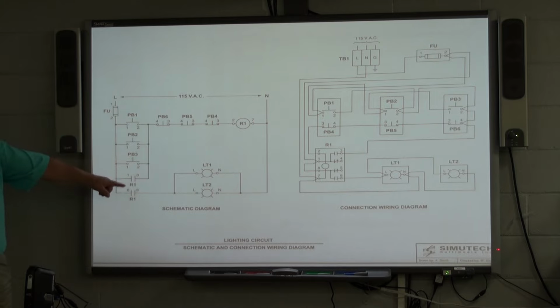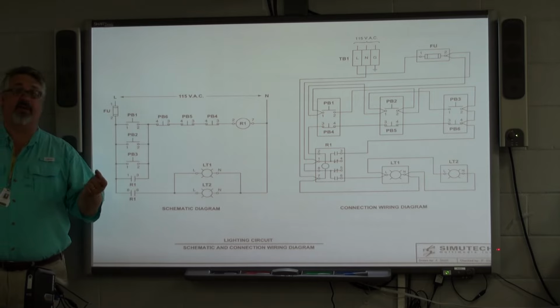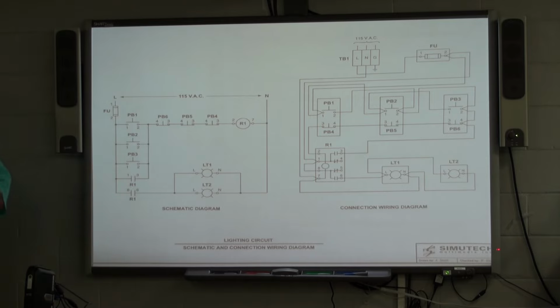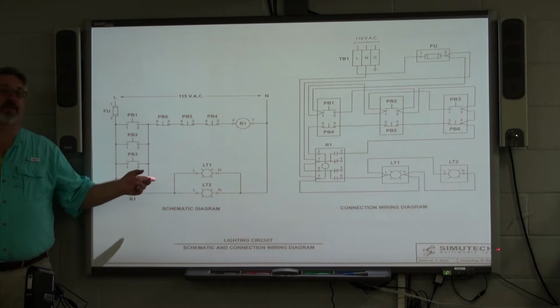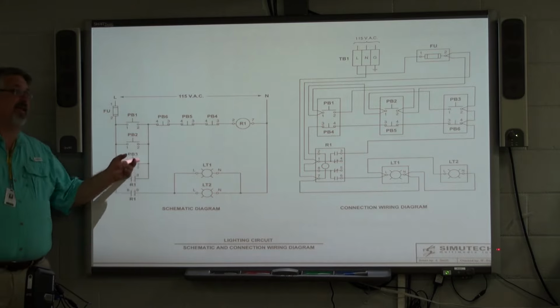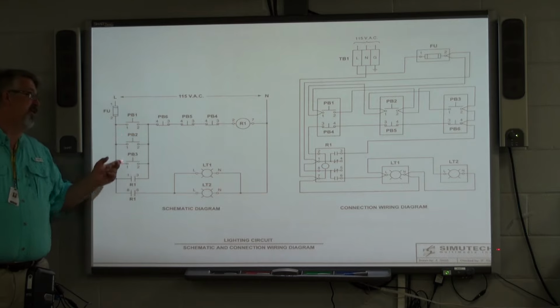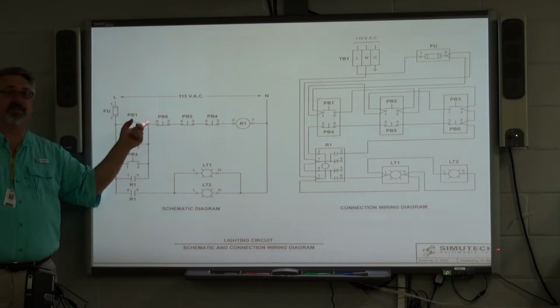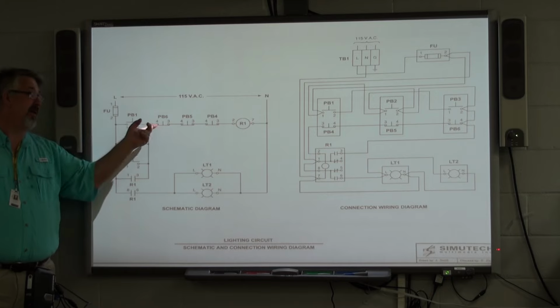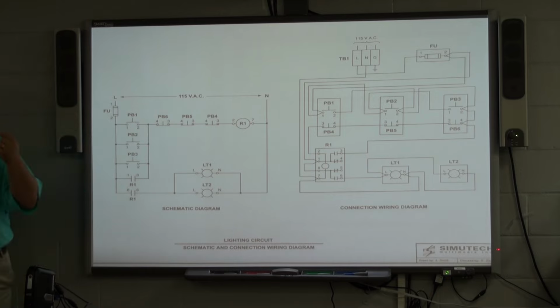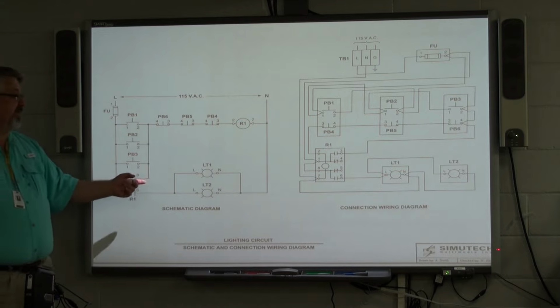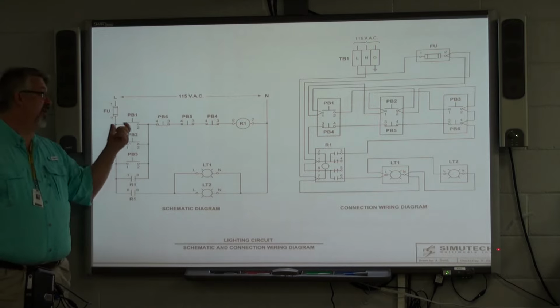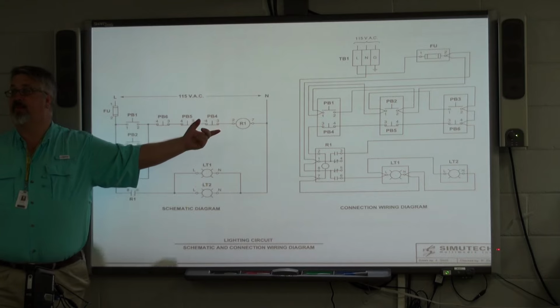Well, R1 and R3, our pin 1 and pin 3 of R1 are also contacts. This is what we call a double pole relay. And we're providing 120 volts here. So what that does is it keeps this rung, and this is called a rung in ladder logic diagram, true. So it latches the 120 volts that we're providing to the coil.